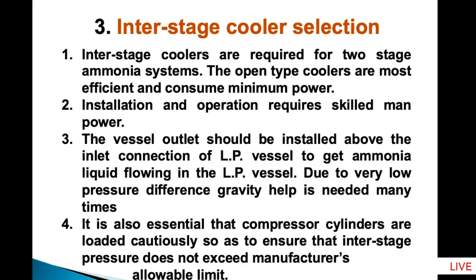So interstage coolers, as I mentioned, are required for two-stage ammonia plants, and the LP vessel outlet should be installed above the inlet.